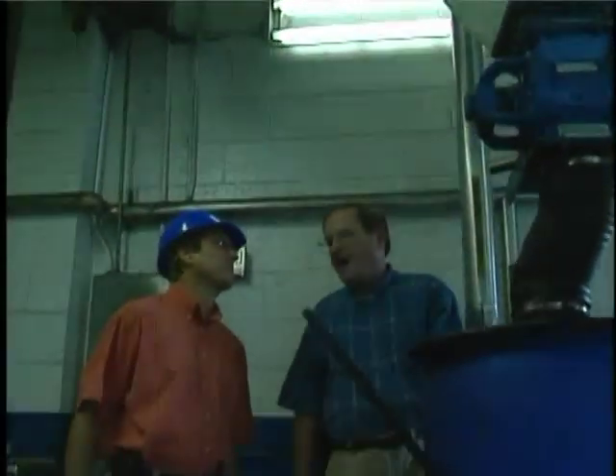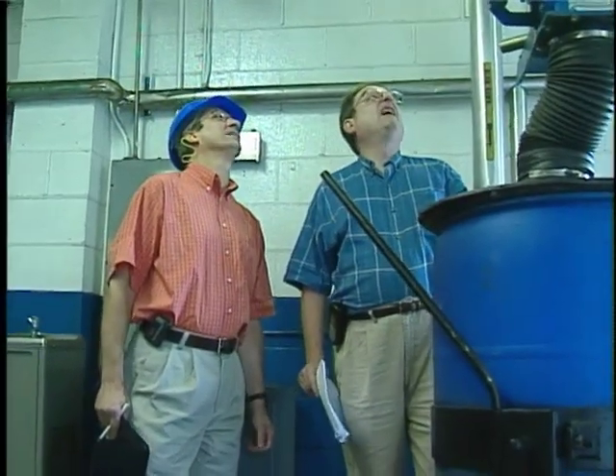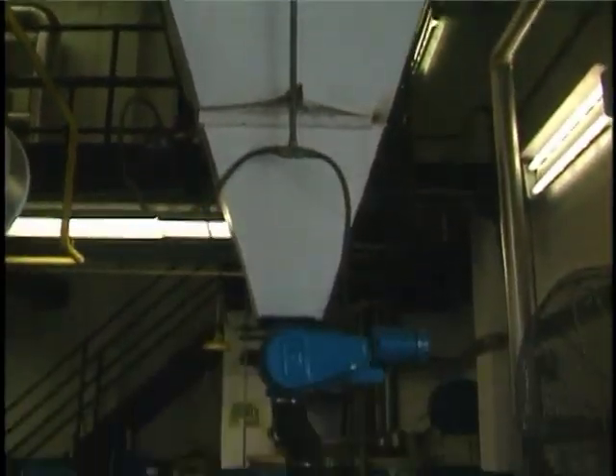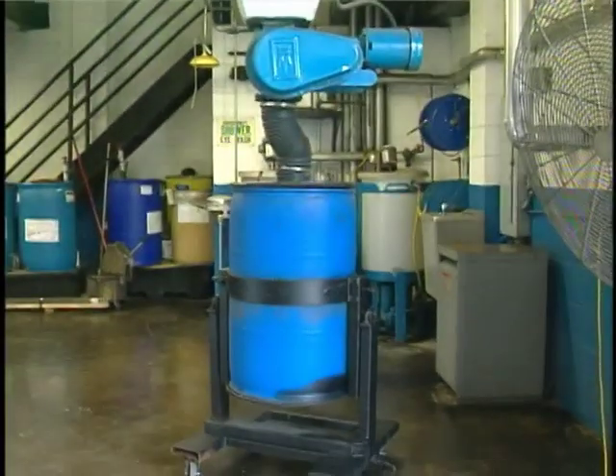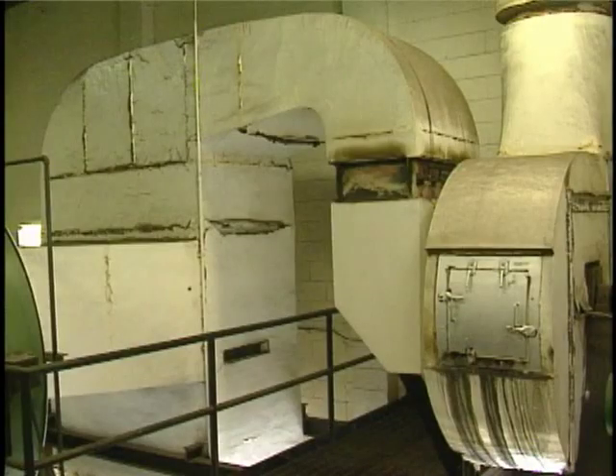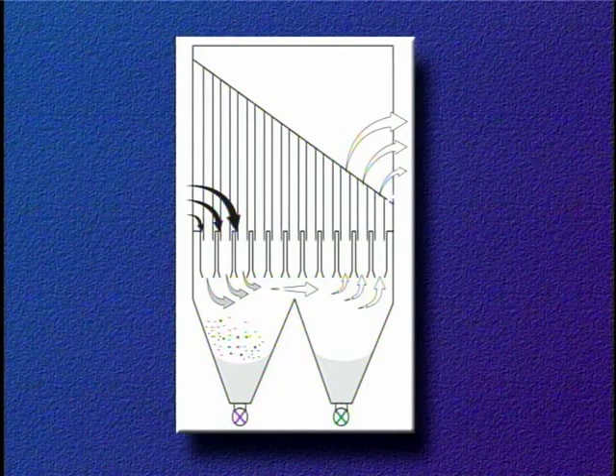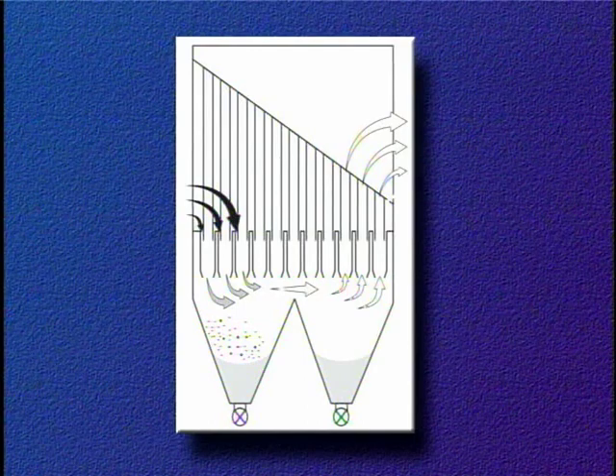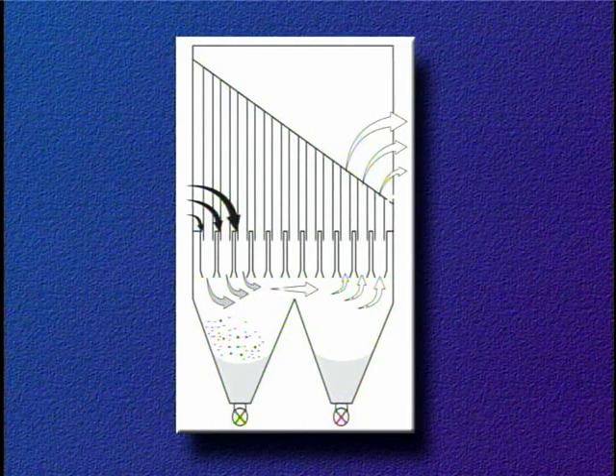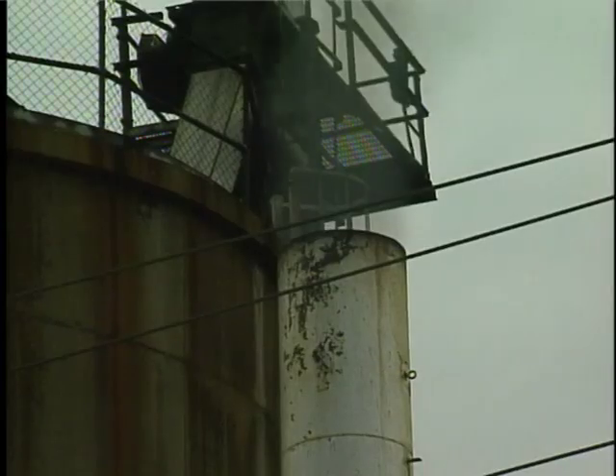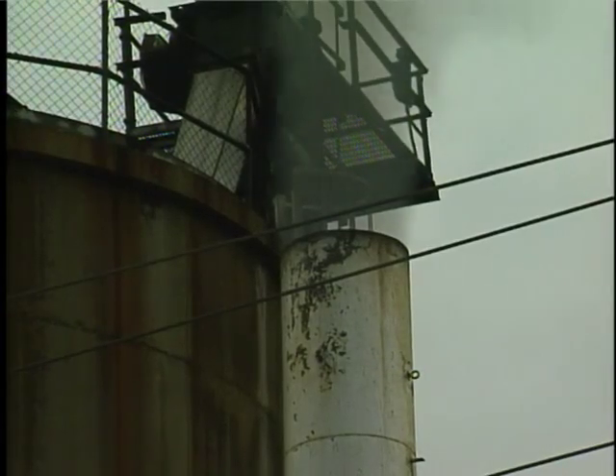Re-entrainment of collected particles may occur with air infiltration below the lower tube sheet of multi-cyclones or through the solids discharge valve of any cyclone. The inspector should also be aware of a design problem referred to as cross hopper recirculation. In very long multi-cyclone collectors, there is a significant difference in the lengths of the exit tubes at the front and back of the collector. Since the longer exit tubes will have a greater flow resistance, air may flow out of the solids discharge of the front cyclones and into the bottom of the back cyclones, entraining particles into the exiting gas stream.